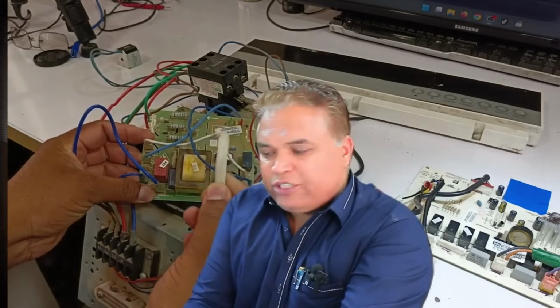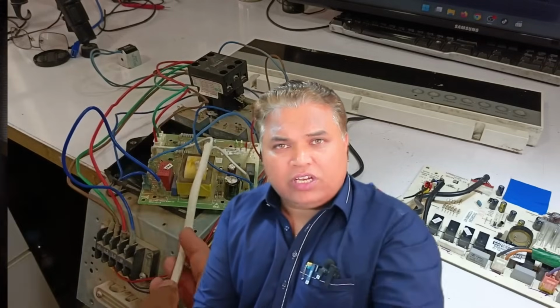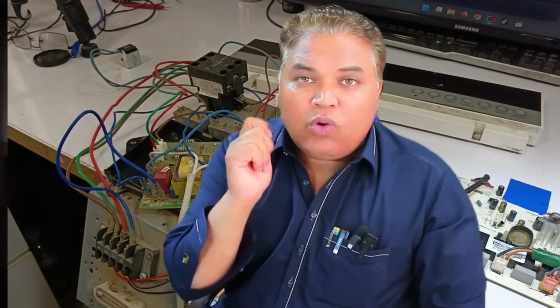The third fault is that if, for any reason, the high-pressure switch shuts off or stops working, it will cause the neutral connection to be missing at the indoor unit. When the indoor unit does not receive neutral, the optocoupler will not activate, and this will again cause the F1 error to be displayed. These are the 3 reasons that can cause an F1 error.